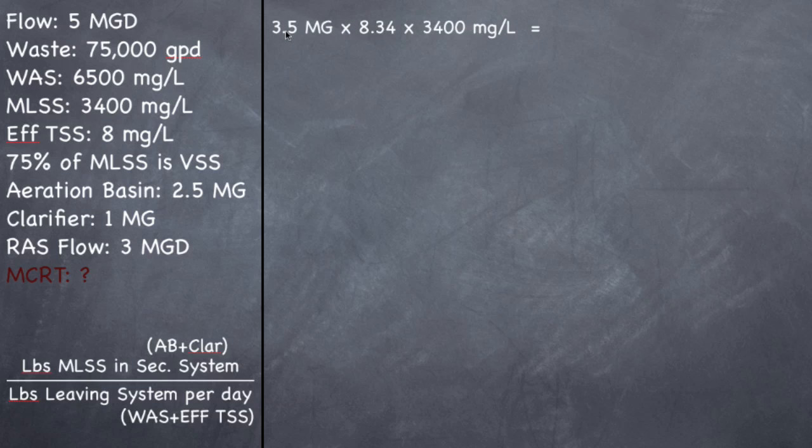So we take 3.5 million gallons. Now some of you might be wondering where did I get this 3.5? I don't see a 3.5 million gallons on anything they gave me. Well remember, it's aeration basin plus the clarifier, so I went ahead and added those two together. You can do them separately, figure out how many pounds are in the aeration basin and how many pounds are in the clarifier and then add them, or you can just add their volume in the beginning and only do one pounds formula instead of two. This is kind of a faster way.